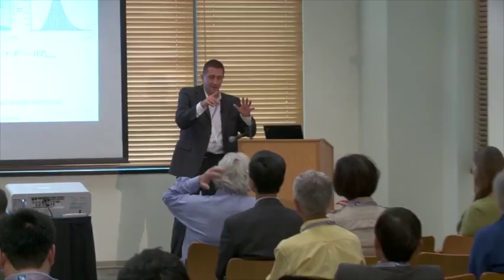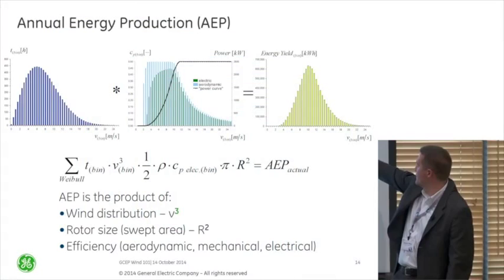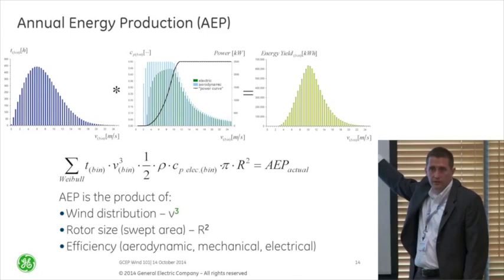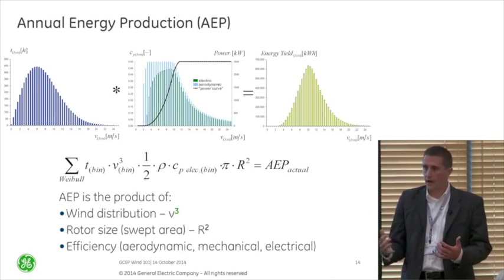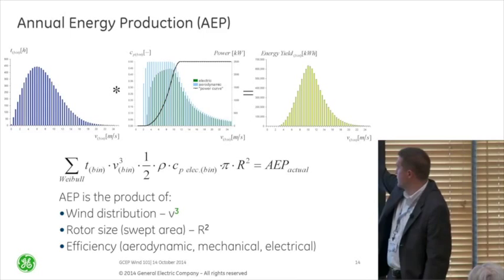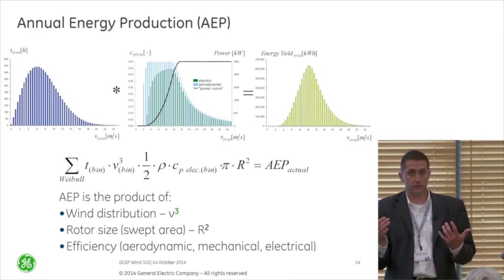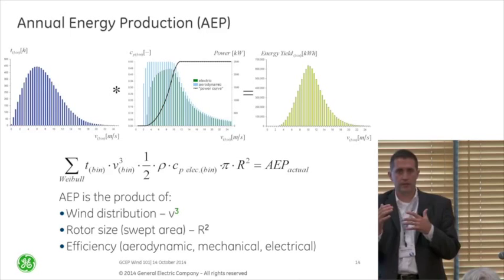A wind turbine is only as good as its annual energy production. If you take the wind distribution from the top left, overlay the power curve, you come up with an energy yield — and that's really what we do for any project we're looking at for a customer. The interesting thing is that most of the energy you create is probably between 8 and 12 meters per second. Between 8 and 10 is really important for CP, while between 10 and 12 is really important in how you handle your peak shaver and control aspects.